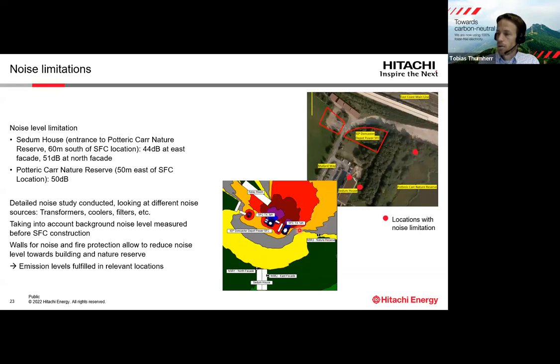And at the bottom here, you see the result of the noise study that was done. Basically, what we have done in the project is that the fire protection walls around the transformers have also been used as noise reduction walls. You can see very nicely that the noise emission towards the nature reserve and the building is very well damped, and the noise emission limits can be met at the specified locations. So I think this example shows that it's quite important to know the emission limits, the requirements, early on in the project.